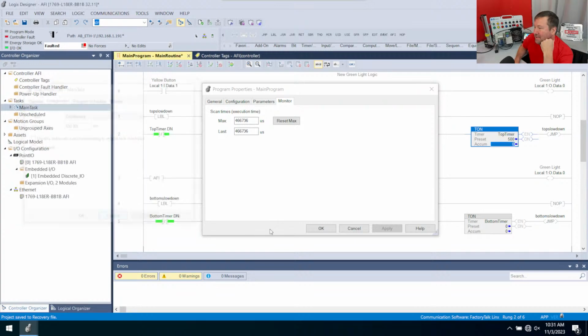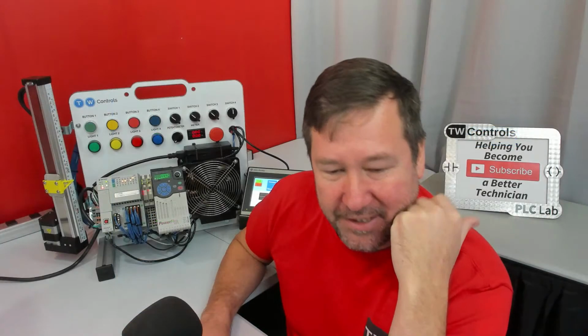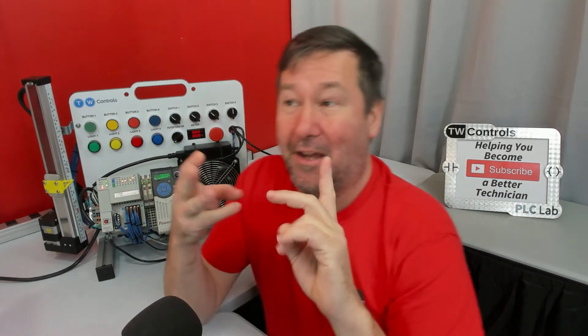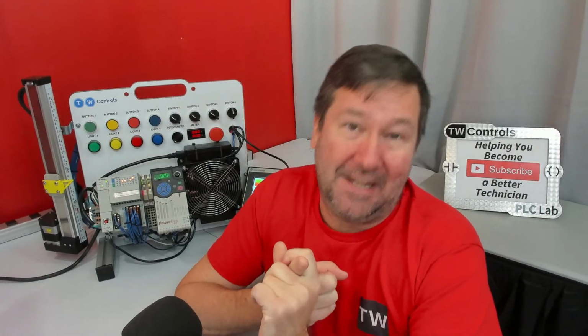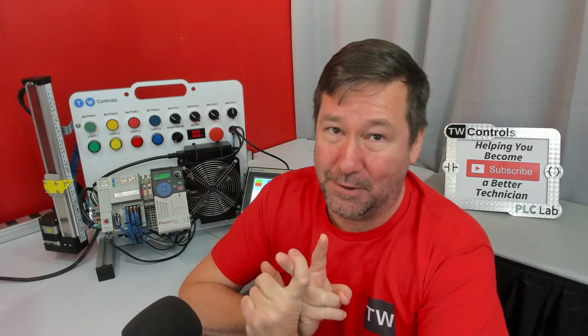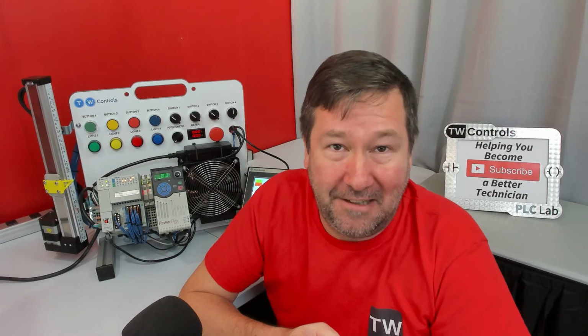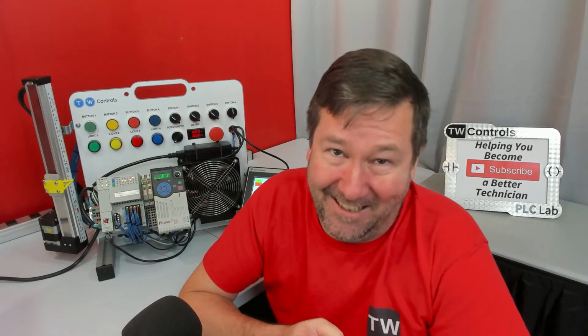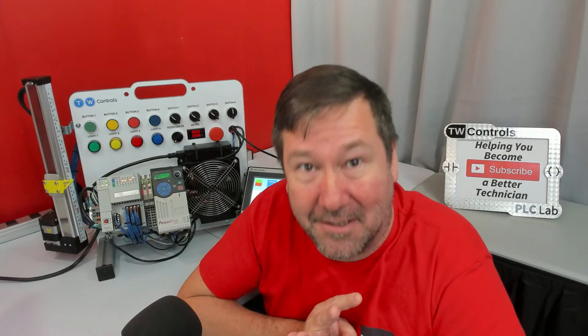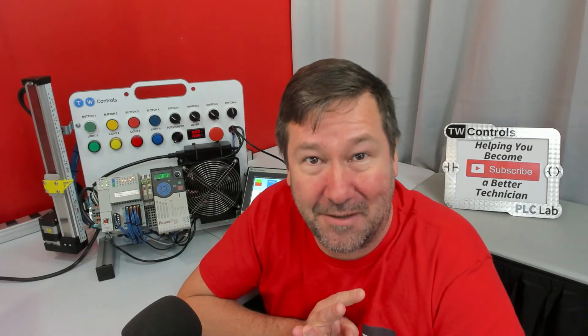Really, if nobody has any other questions, that's the big thing I wanted to hop on here for, to talk about what happened last week and hopefully get some of you to see, okay, I hope there are 3 takeaways from this. I hope you do understand how program scan works. I hope you will begin to agree with me that we shouldn't just say, well, thou shalt not use an AFI. No, we need to understand the AFI. And in this case, yeah, it does make an instruction false. It does not disable the rung. And yeah, while duplicate destructive bits may be bad, we may need to understand them because you may run into one of them out in the field.